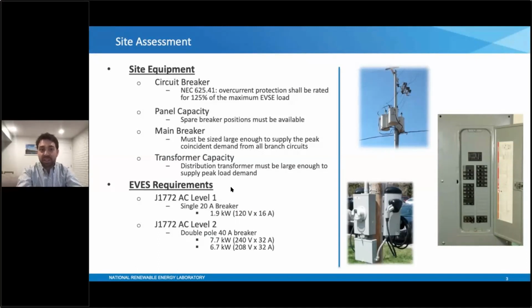One of the most important things is that overcurrent protection, or the circuit breaker, must be sized for 125% of the maximum EVSE load. This circuit breaker must also be servicing a dedicated circuit.